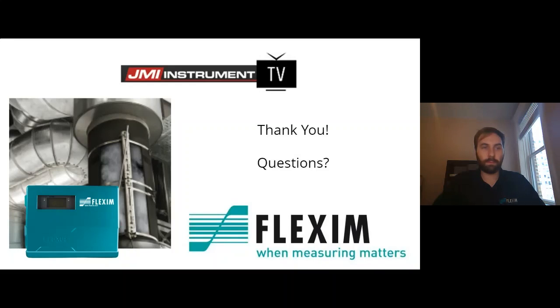If it's a liquid with some gases in it, there's no true way to do that. With liquids and gas, you can sometimes use Doppler mode. So if it's a liquid and it does have some aeration, and you can't seem to get a good measurement with transit time, you can put the meter in Doppler mode. And for Doppler mode, you have to have bubbles, or you have to have particles or solids in the stream in order for Doppler to work. So that's an option. Not always does it work that well if you're starting to aerate too much, but it is an option.